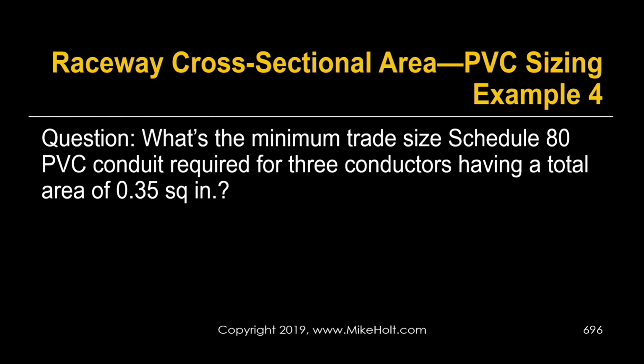What's our minimum trade size Schedule 80 PVC required for 3 conductors having a total area of 0.35 square inches? Now, first thing I pay attention to is, hey, we're not talking about an EMT anymore. We're talking about Schedule 80 PVC. So we're going to have to find that table. So hopefully you've noticed that detail and are already looking for our Schedule 80 PVC, which starts down at the bottom of page 718 and continues on top of page 719.